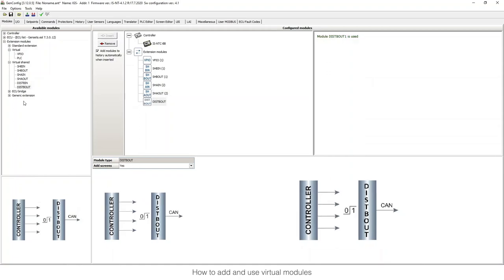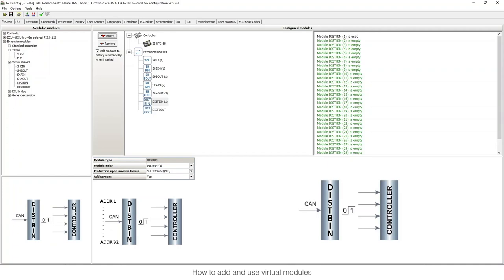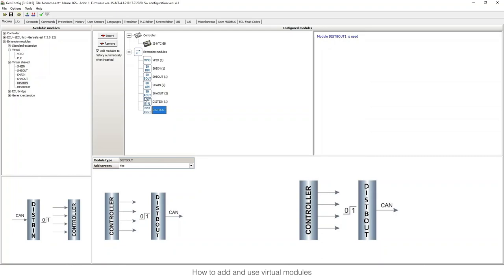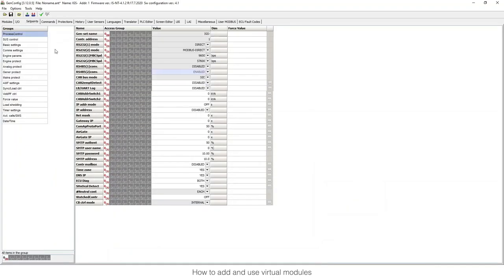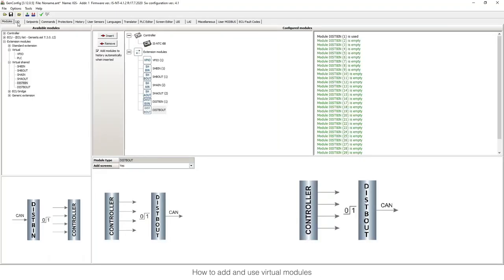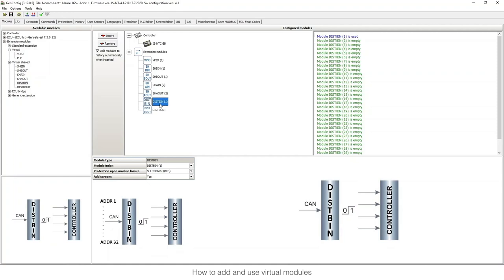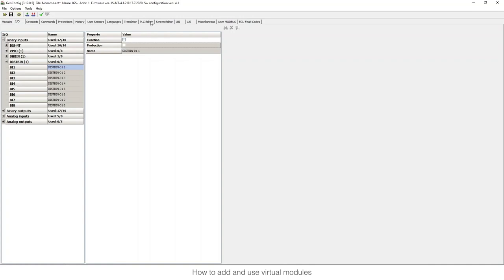You just need to add the distributor binary output and then add distributor binary inputs. The binary output has no index because the index is taken from the controller address. You can check this in Setpoints > Basic Settings > Communication Settings, where you can see the controller address. So the controller will send its own information based on its address. In the other controllers, you specify which controller address you want to read from. You go to inputs/outputs and configure it as normal.